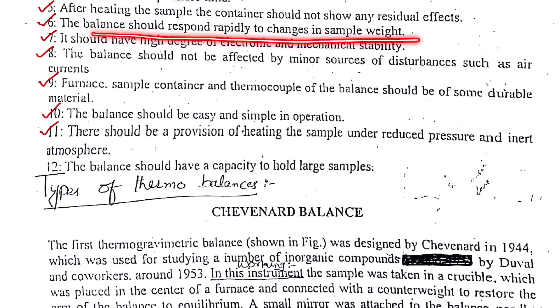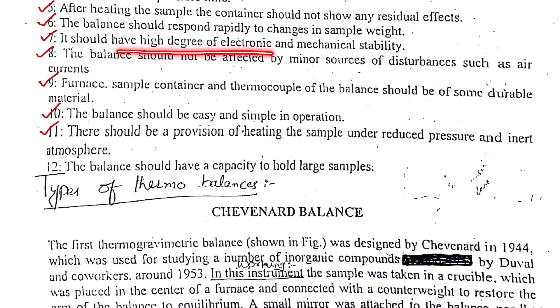The balance should respond rapidly to the change in sample weight. This also falls into the category of sensitivity — the heating should increase linearly with small incremental changes, and correspondingly the balance should show the relative changes in weight very smoothly and rapidly. Next, it should have a high degree of electronic and mechanical stability, so that voltage or weight changes do not destabilize the instrument.